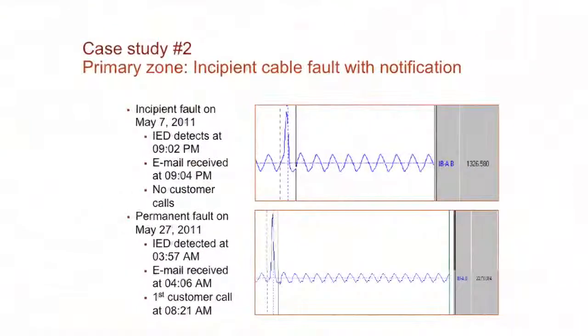Now let's talk about the May one. May was 9 p.m., and the email was received at 9:04 p.m. - 2 minutes - and no customer calls. You can see it's about over 1,300 amps, one phase B. Then May 27th, it happened again at 3:57 a.m. Actually, the first customer call didn't happen until 8:21 a.m. because this fed a park - I guess that's when they did their walk in the park.